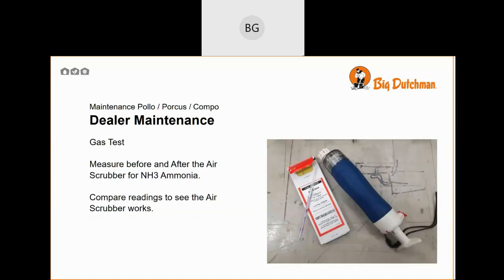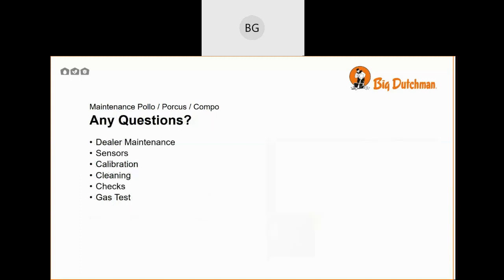Gas testing. Measure before and after the air scrubber for NH3 or ammonia. Comparing the readings to see the air scrubber works. Comparing these two readings will tell you the percentage of effectiveness of the air scrubber and how well it is working. Are there any questions on the maintenance?